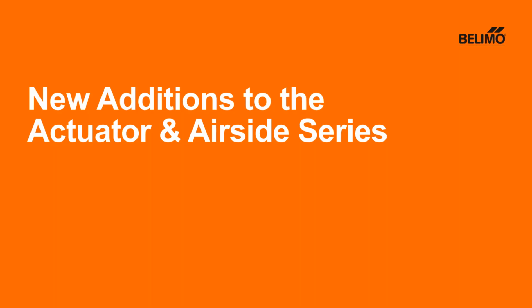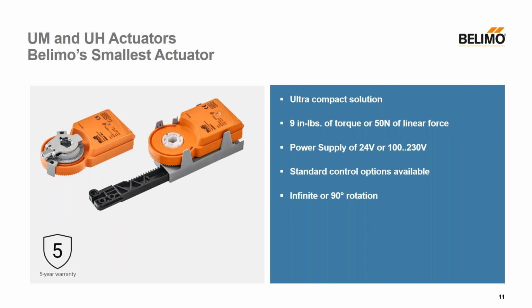Now we'll look at the new additions to the actuator and airside series in the PGPL. So when you flip to page 1-6 of the non-fail-safe damper actuators, you'll spot the new UM and UH series. This is a great new solution for very compact equipment integration and more. The small footprint with thin design offers 9 in-lbs of torque or 50 Newtons of linear force for the UH model. We have model-specific power supply options of 24 volt and 100 to 230 volts. We offer standard mechanical connections of a universal 1/2-inch clamp or an 8mm form fit, or flexible with linear. It is wire harness ready with the built-in Molex Mini Fit Junior connector, and this enables reduction of OEM development time.